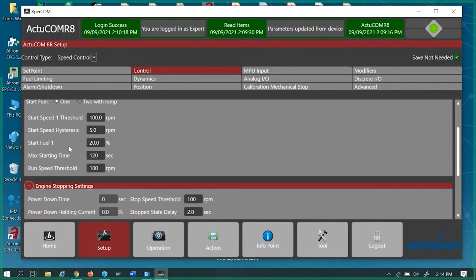your change of everything, your start fuel. So on our GOV, we can say, hey, I want an actuator kick to open my valve up so far because I need a little bit more fuel right when we start. We can use this the same way. If we start at 0 position, like with the carburetor always closed, and then we try to ramp up, maybe we're in a situation where we don't have that much starting air or something like that. We don't want to run our starters very long. You can say, well, jump it up to 20%, 30%, whatever. Let's get that fuel to it real quick, and then just bring it on up. It's kind of like a little actuator cheat.